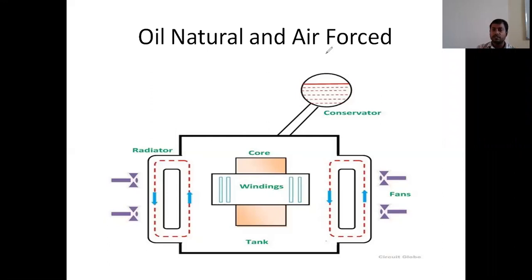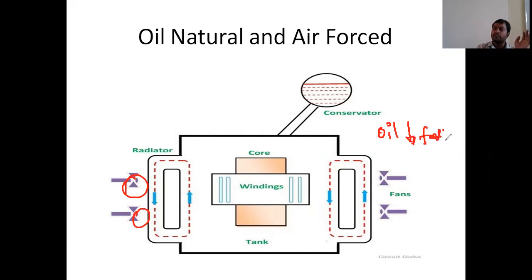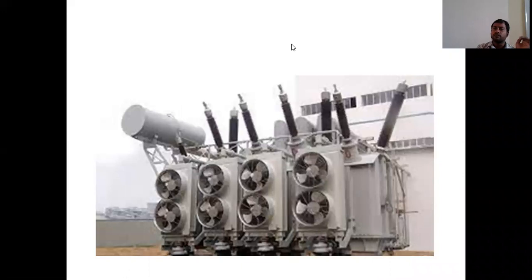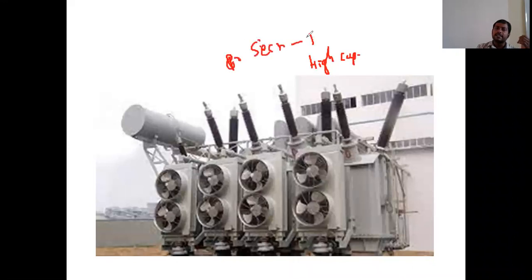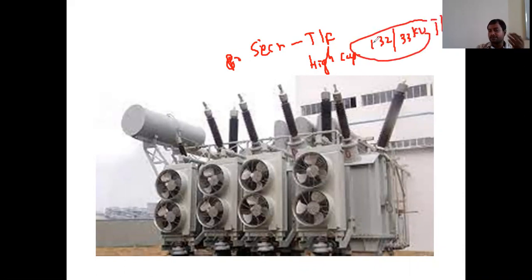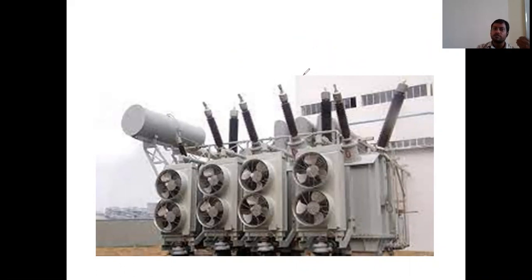In ONAF, by using the fans we provide forcible natural air. The high temperature oil temperature decreases very quickly. This is used for high capacity — secondary transmission side, such as 132 by 33 kV transformers. In the primary or secondary transmission side, this type of cooling system is used. You can see the radiator and eight fans available.